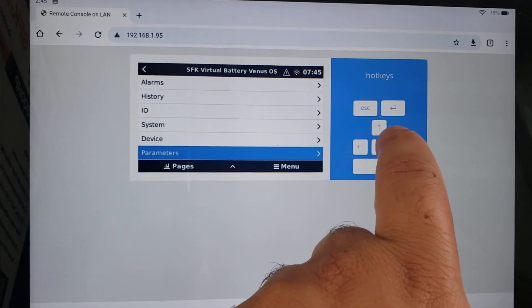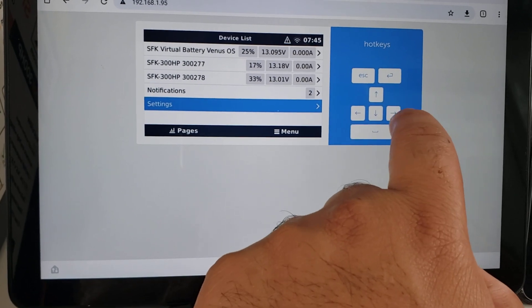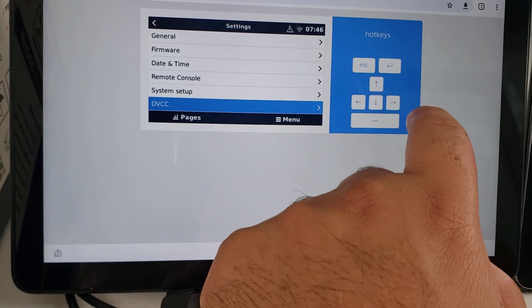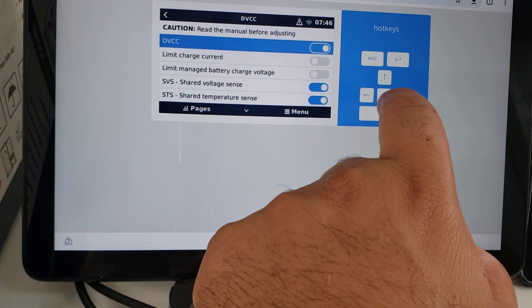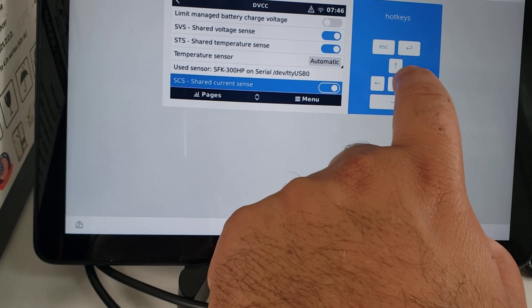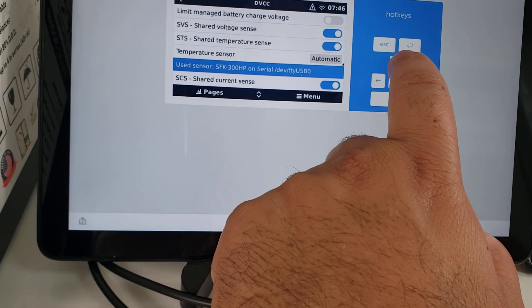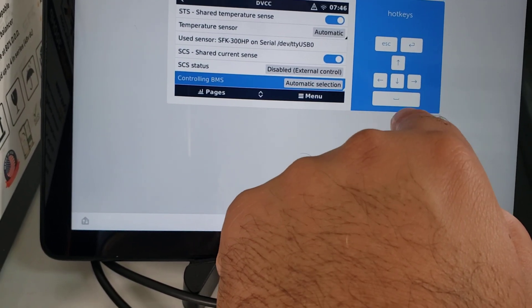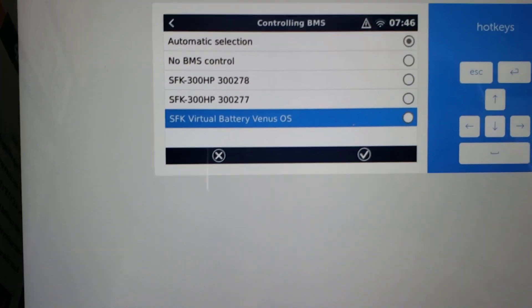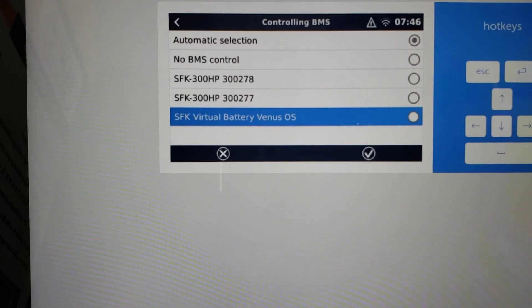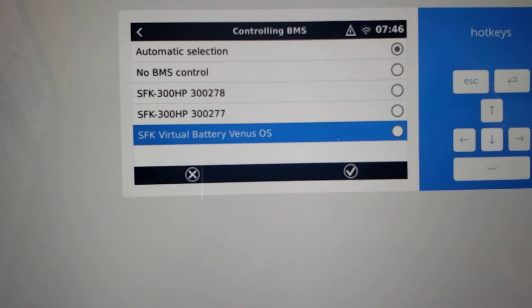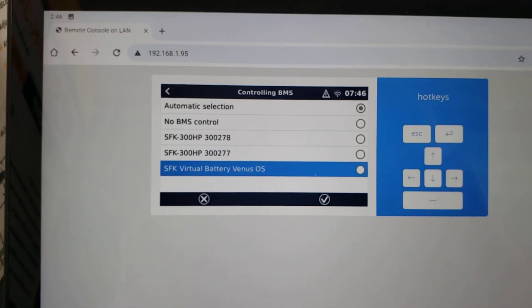And then like I said, just go to the system for the settings, and you can assign this battery to the DVCC as your main controlling BMS. So if you enable this, you can choose which one is it going to be. So instead of use sensor, you can go in here. Well, temperature sensor, well I guess you could say that that's fine. But controlling BMS here, you can go in and set the virtual battery as the main controlling BMS. So it will take sort of events from any available battery. If any battery throws an alarm, low state of charge, it will report back to the virtual battery, and that way you can sort of have that. And then also this can also control the thing, so you can set that up.